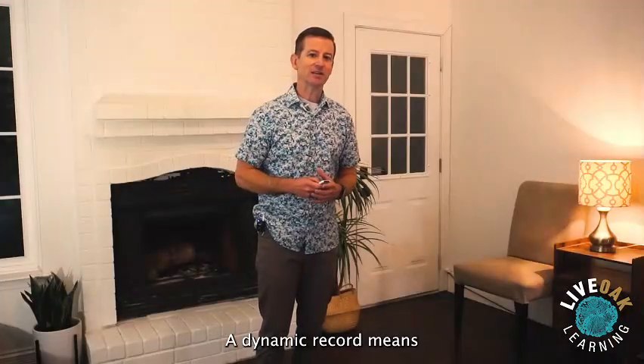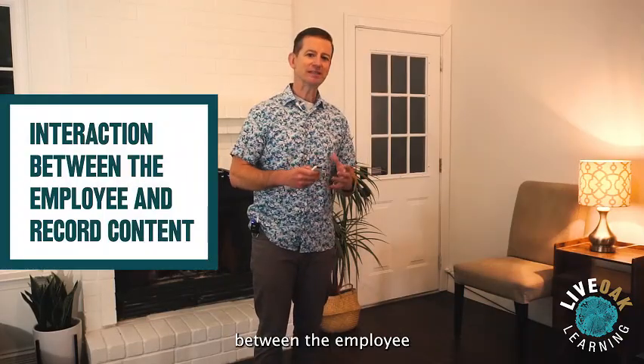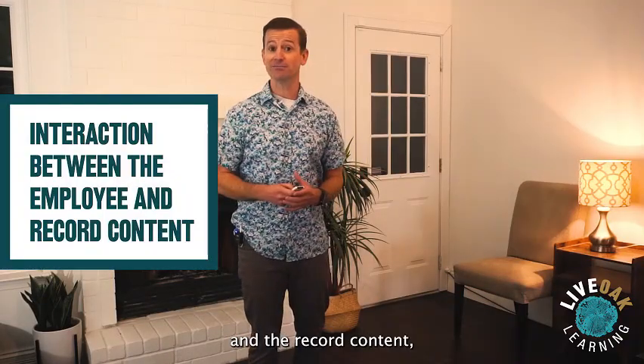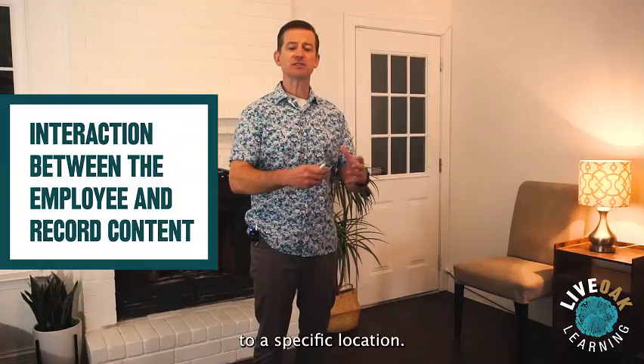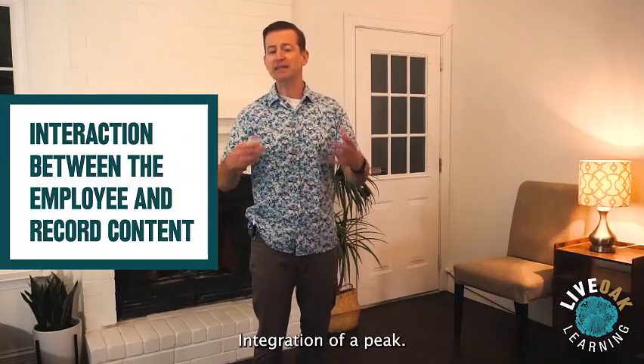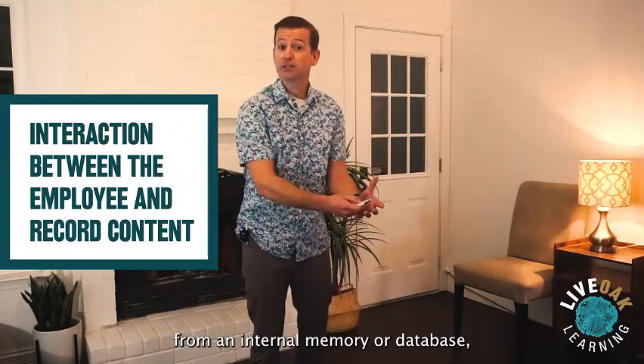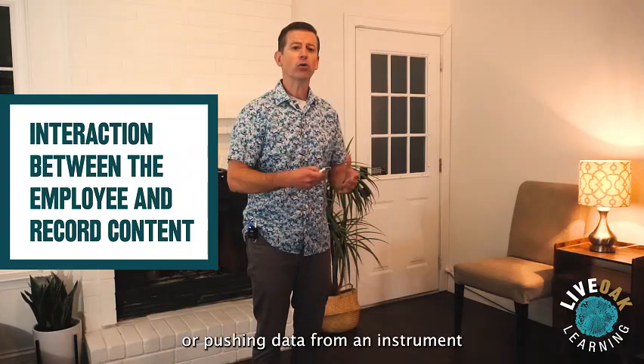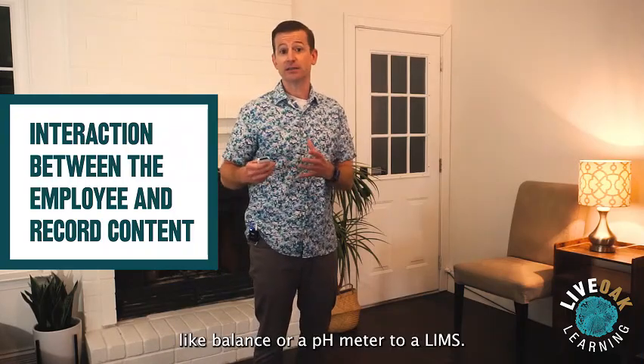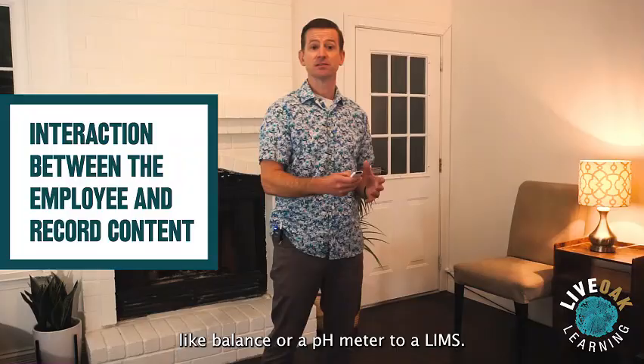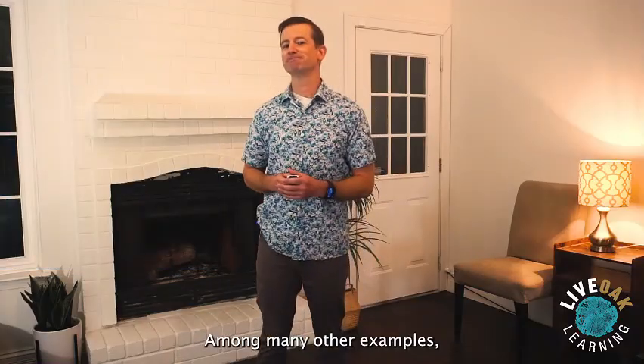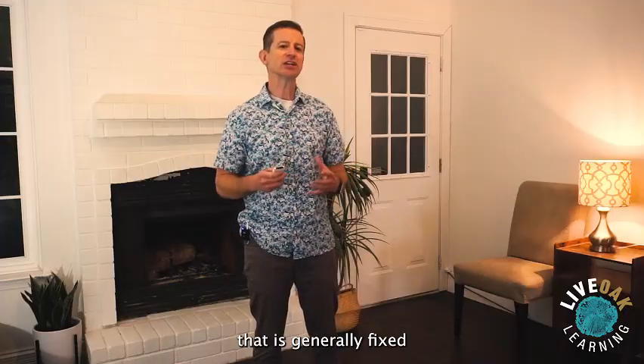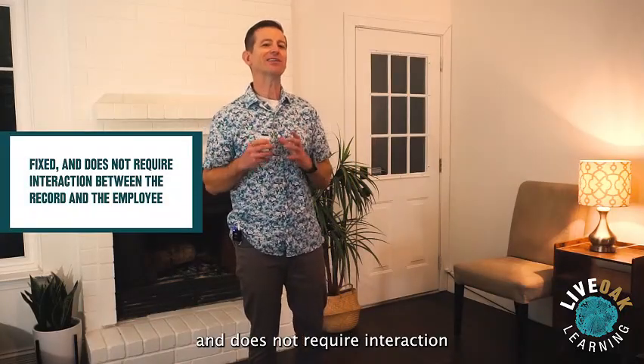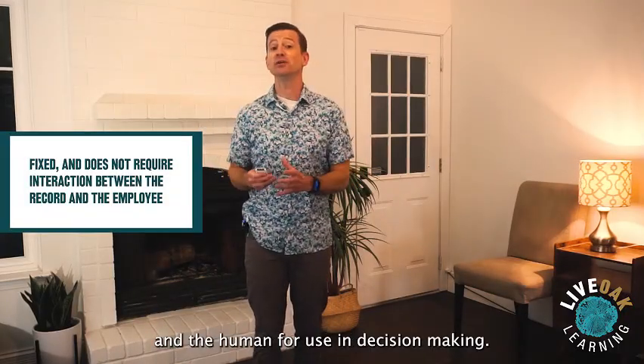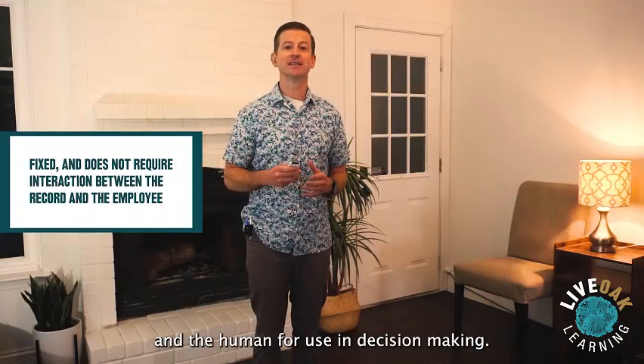A dynamic record means there is interaction between the employee and the record content, such as saving the record to a specific location, integration of a peak, printing the record from an internal memory or database, or pushing data from an instrument like a balance or a pH meter to a LIMS, among many other examples. A static record, on the other hand, is a record that is generally fixed and does not require interaction between the record and the human for use in decision making.